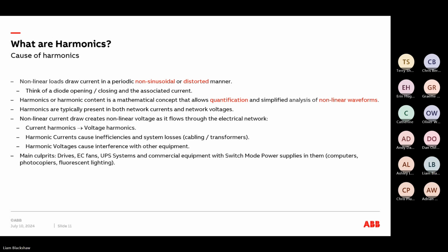So effectively, when drawing current harmonics, as a result of that, you will get voltage harmonics. And harmonic currents cause inefficiencies and system losses, so things like cabling and transformers, when we may start to overload those. But the harmonic voltage aspect of it is what causes interference with other equipment as well. The main culprits, obviously, variable speed drives. It could be EC fans, UPS systems, commercial equipment that has a switch mode power supply in it, so things like computers, photocopiers, and fluorescent lighting.